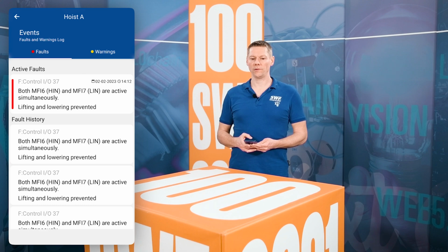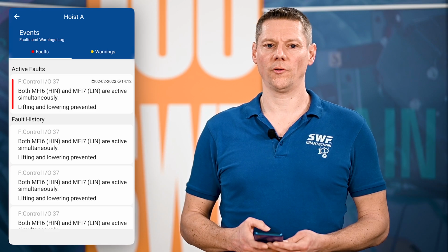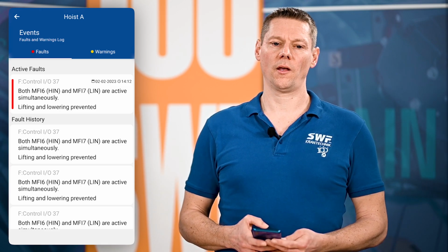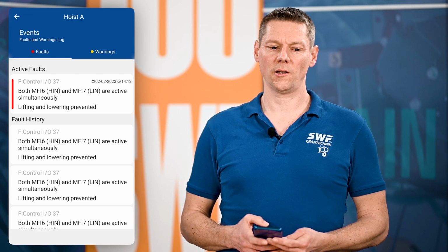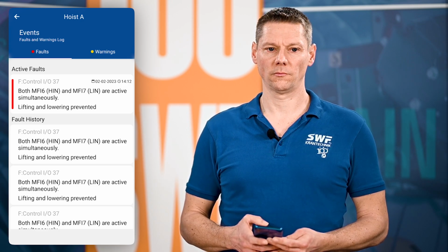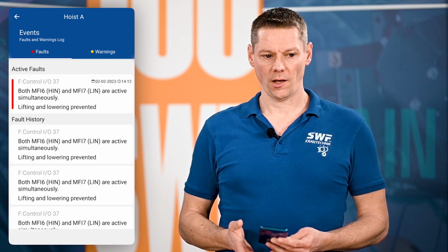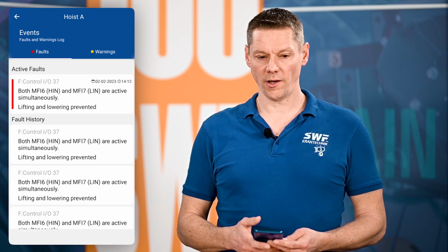If the OMNI control detects a fault, it will be shown here in the app. We get the fault information with a fault number and a short message, a short description about the fault itself. A timestamp is also given, and together with the service manual we can check where the fault is coming from. If the fault is gone, the fault will move from the active fault to the fault history.